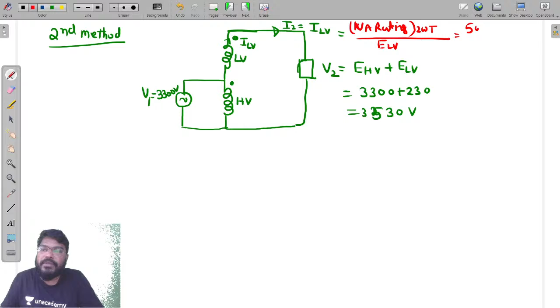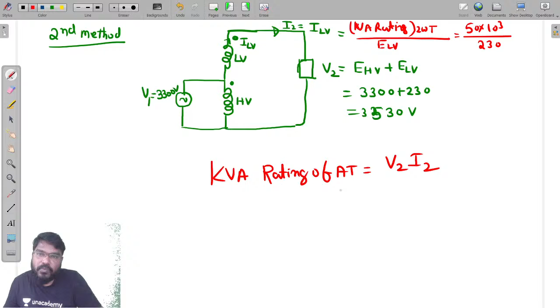Now the kVA rating of the auto transformer is equal to V2 multiplied by I2. V2 is 3530, into I2, which is 50 into 10 to the power of 3 divided by 230. So it is equal to 767.4 kVA. Like this also we can answer. In the two methods we can answer. Very important: any problem we can answer by using the transformation ratio as well as by using circuit analysis. Whatever you feel easy, you can go through that method.